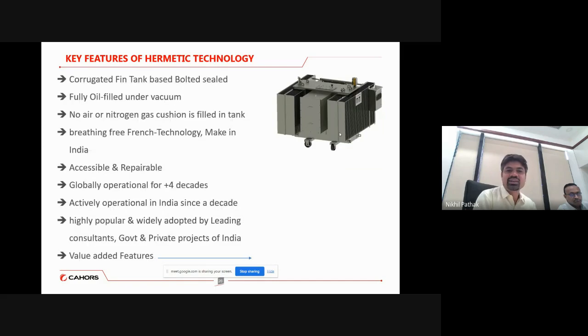Now let us understand the key features of the hermetically sealed technology, how it is elaborated and how it is spelled out. That is important to understand. Basically, we are offering the hermetically sealed transformer with corrugated fins, and the sealing we do is a bolted sealing. Alternatively, a few manufacturers do offer welded sealing, but we don't offer that, because bolted sealing also gives accessibility for repairing. So our hermetically sealed transformers are also accessible and repairable. That is the good part of it. As long as it is a bolted cover, in case of any troubleshooting, it will always have an open access for repairing, in case it is required at site.